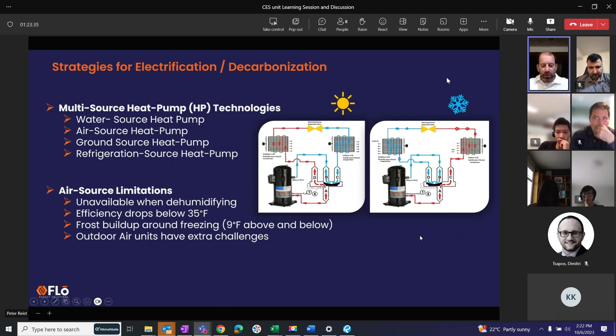And so knowing that concept, we're living in between, right? We're bringing in outside air because we have to, but because we're also bringing in recirculation air, we actually temper that air so we can keep our heat pump running longer and at lower temperatures. But watch your rating sheets. We see it every day of the week, heat pumps only providing the recirculation value. And of course, they have great low temperatures. But as soon as you put outside air on them, those numbers fall apart. So just keep your eye on that very carefully. Okay. We make those units too. So that's why we understand it so well. So that's one technology.